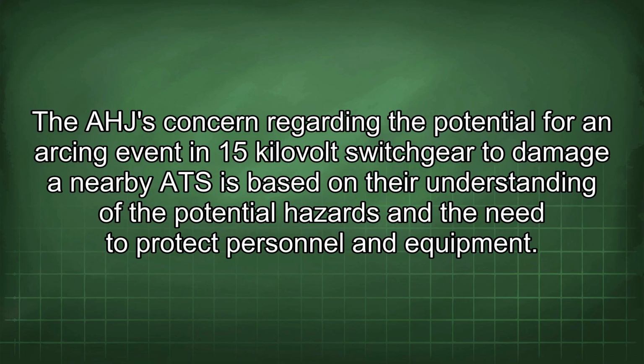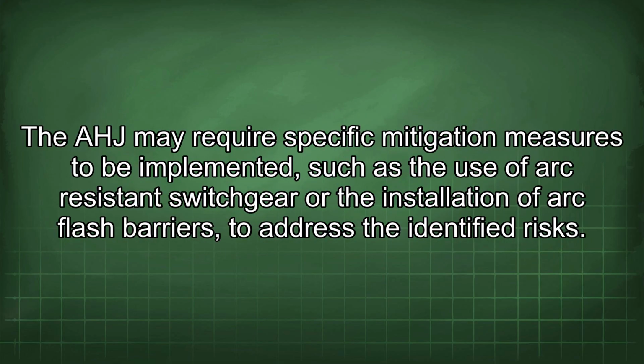The AHJ concern regarding the potential for an arcing event in 15 kilovolt switchgear to damage a nearby ATS is based on their understanding of the potential hazards and the need to protect personnel and equipment. The AHJ may require specific mitigation measures to be implemented, such as the use of arc-resistant switchgear or the installation of arc flash barriers to address the identified risks.